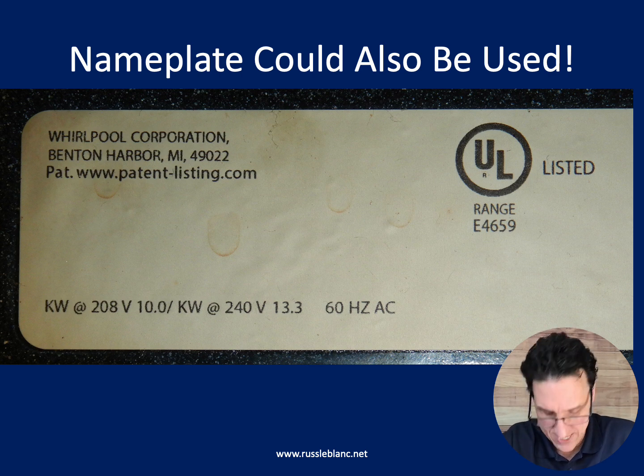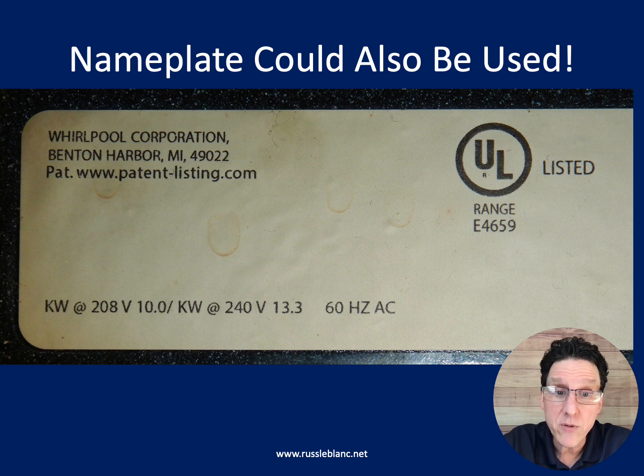Now, if we don't want to use the table, because it is permissive, you're not required to use the table, but you have permission to. If you don't want to, you could use the nameplate. You could absolutely use the nameplate to size your branch circuit. And so let's take a look at this nameplate and size the branch circuit and see what happens.